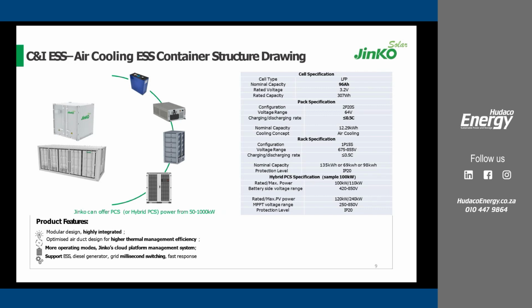The rated power of the PCS can be 50 kilowatts, 100 kilowatts, 150, 250, and 500 kilowatts. We also have the maximum output power, that is continuous power, not for a short period of time, which can be up to 110% of its rated capacity. So for example, for the 100 kilowatt unit, we can output up to 110 kilowatts continuous power.